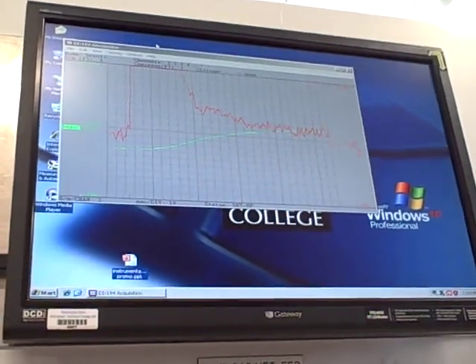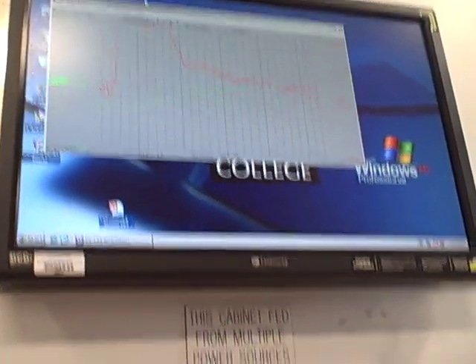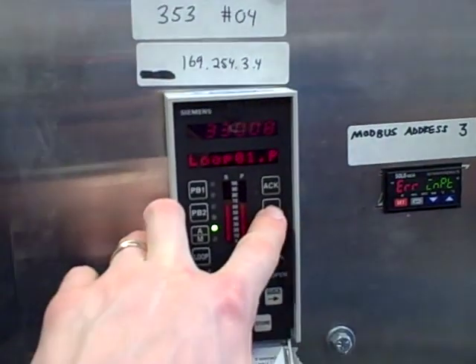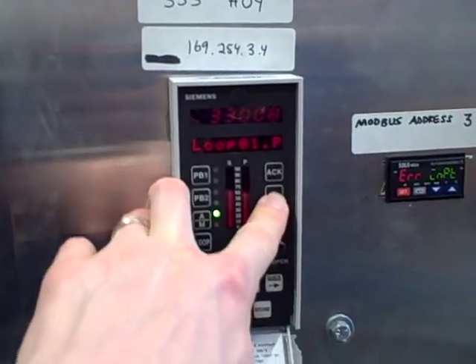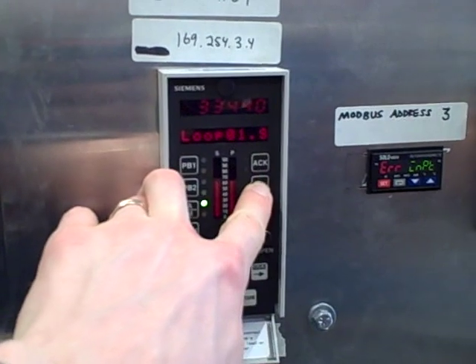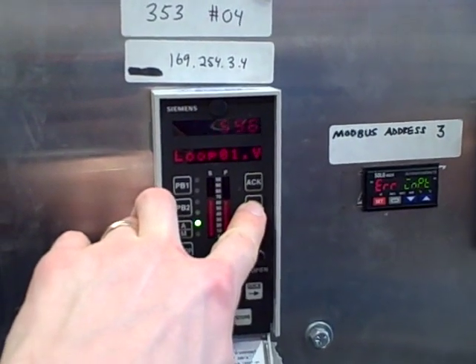One thing on your trend display, we don't show setpoint because we don't have an analog setpoint voltage to measure. But we can look at it here. We can compare these two. Process at 330 degrees and setpoint 334. So we're within a few degrees of setpoint.